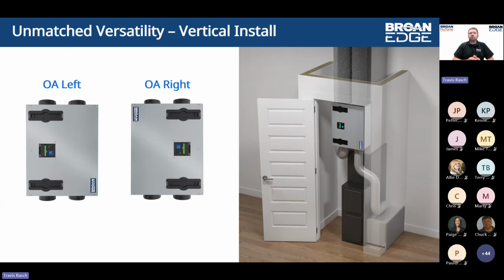And the other thing to note too is you can kind of see, again, maybe depending on your door swing of that closet as an example, or maybe there's some other obstructions, you do have the ability to rotate the Edge 180 degrees, meaning the outside air could be coming in from the left, up, or be coming in from that upper right portion. So again, depending on the application, depending on how it's installed, do know that you have that flexibility of having that outside air on that left or that right side.